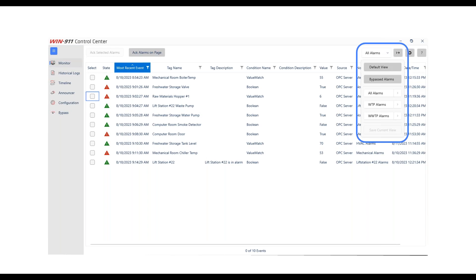The live monitor window has all the same functionality as the log viewer when it comes to acknowledging alarms. You just select the alarms you want to acknowledge, hit the ACK button, and that goes back through to your WIN-911 system all the way to your SCADA system, depending on which one you're using. The performance has been improved quite significantly because we're not querying a SQL database — this is coming directly from the dispatcher module, so these are the alarms that are live in the system at any given moment.